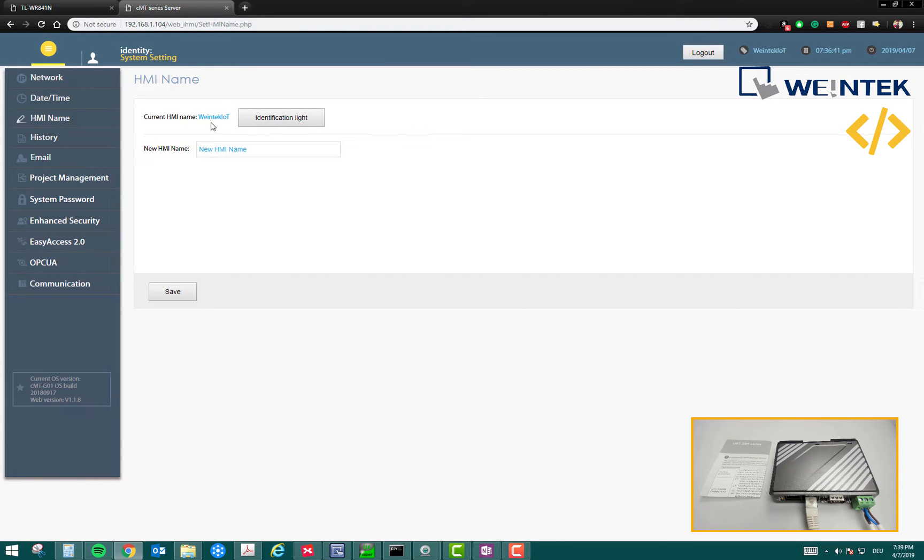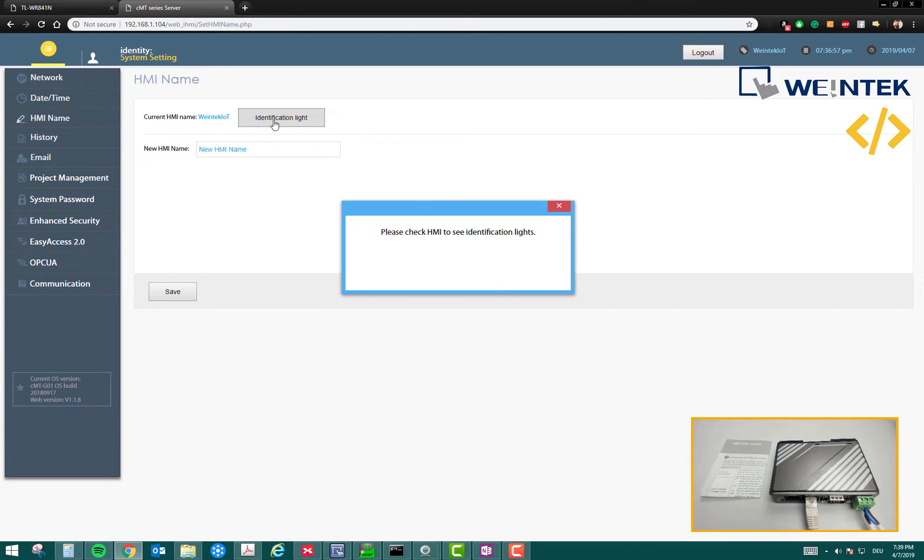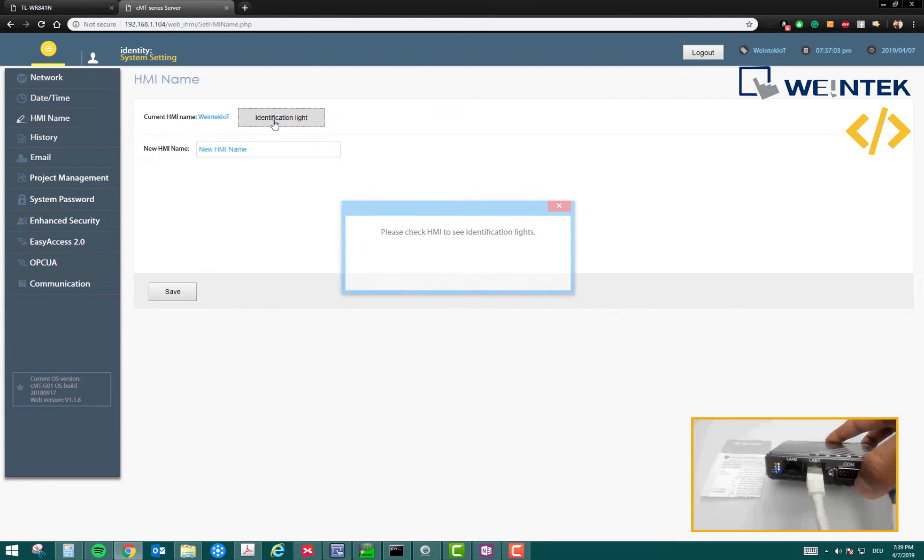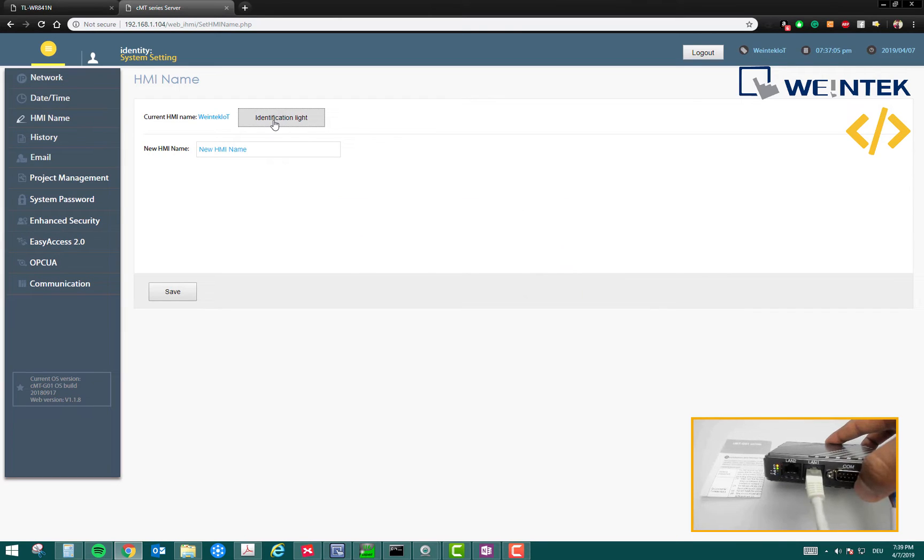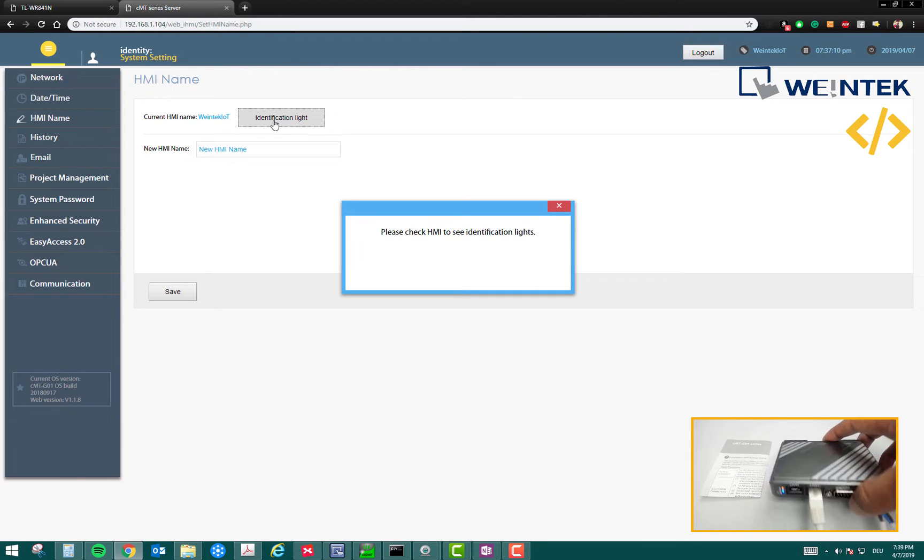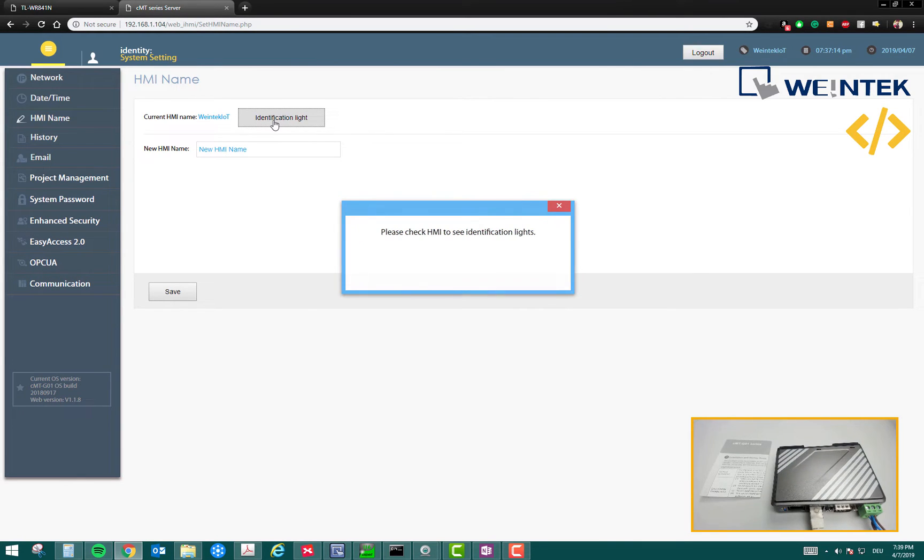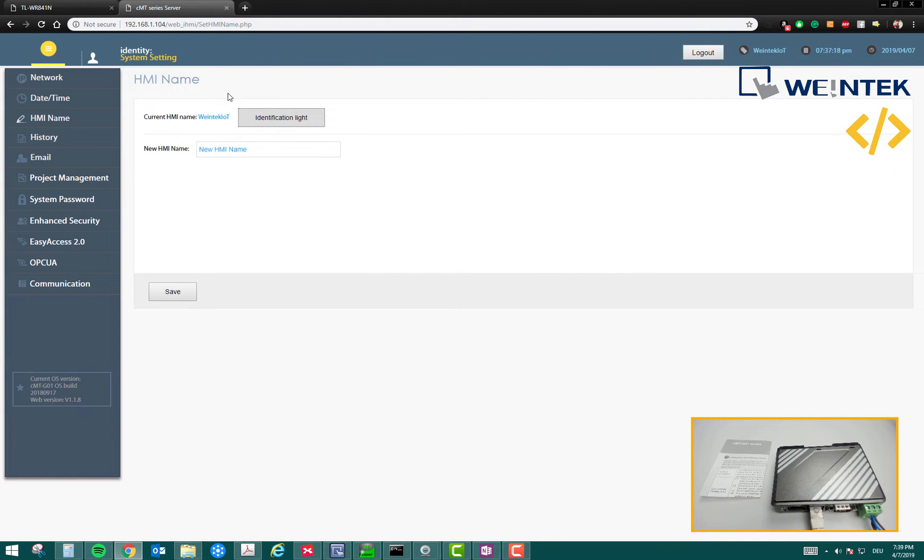Then you have HMI name. You can change the name of your device. I have written Weintek IoT, which is pretty fine. This is the button for identification. Suppose you have 10 IoT devices linked and you're not sure which device is which one, just click this button. Once you do that, you will see on the IoT device an LED blinking. You can see that the green light is blinking. That's how you will get to know which device is linked to your web interface.